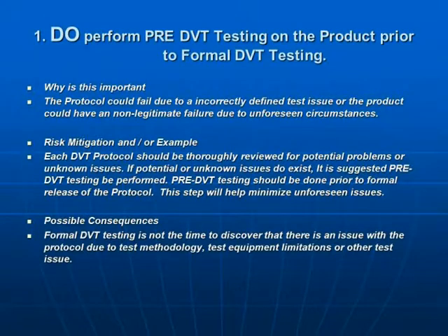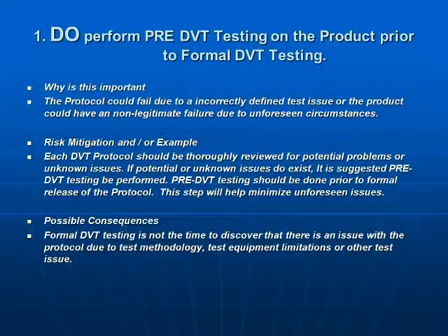The first point speaks to pre-DVT testing. Pre-DVT testing is especially important with respect to new protocols. Protocols should be reviewed to determine if there are any unknown issues with the protocol, the product, or test equipment. Any one of these could cause a protocol failure, and formal DVT testing is not the place to uncover these types of problems.